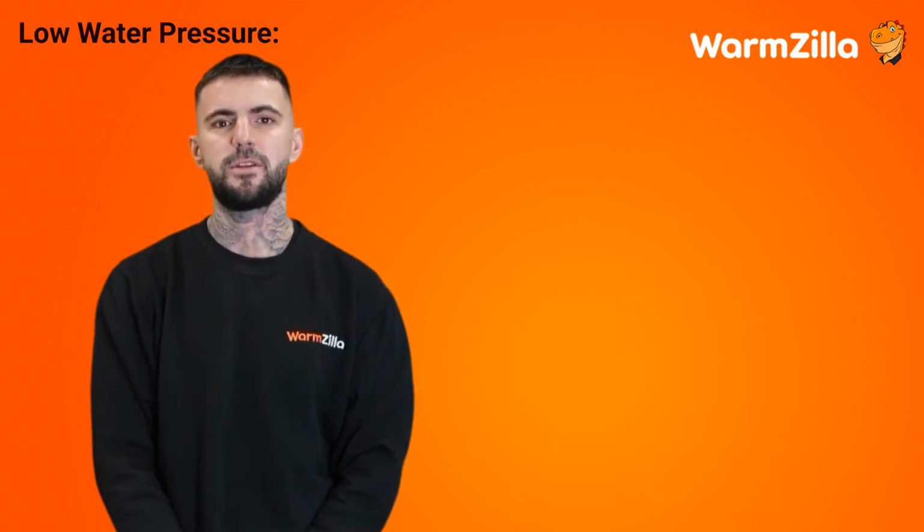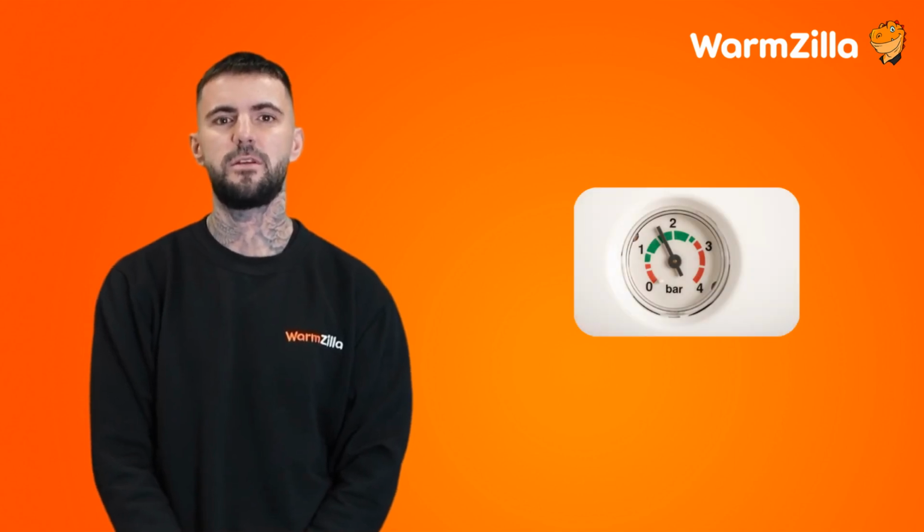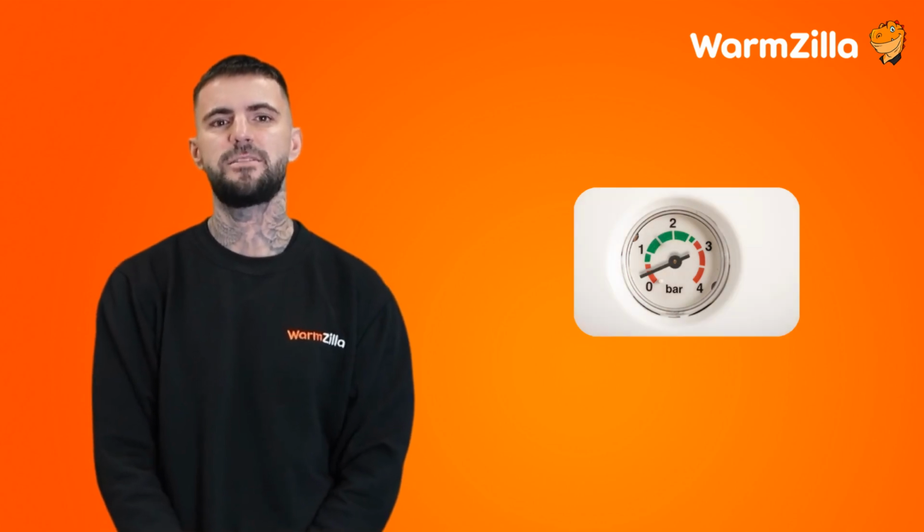Low water pressure. Combi boilers need to maintain a constant water pressure level to ensure they operate as efficiently as possible. For Combi boilers, the usual water pressure level to maintain is between 1.0 and 1.5 bars when cold. If it drops too low, your boiler will activate its lockout mode and need to be repressurized.